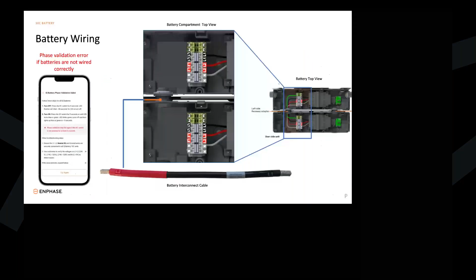What's different from our previous generation products is that because the inverters form the neutral here, we need to wire these in a special way. In the box with the batteries, you'll get a bag with pre-colored wires. You'll see an example wire that's partly red and partly black. We need to connect the L1 terminal of the wall-side battery to the L2 terminal of the user-side battery, and vice versa for L2—red goes to black, so L2 goes to L1. It's really important to get the phasing set correctly.